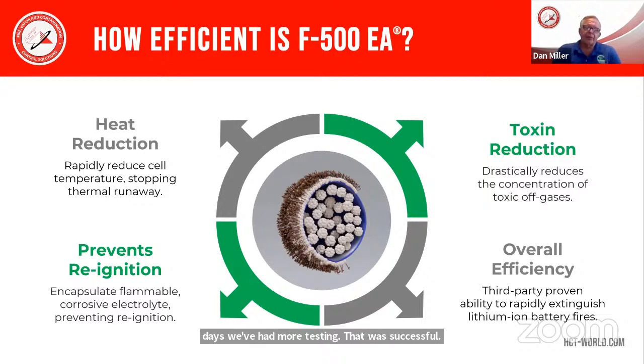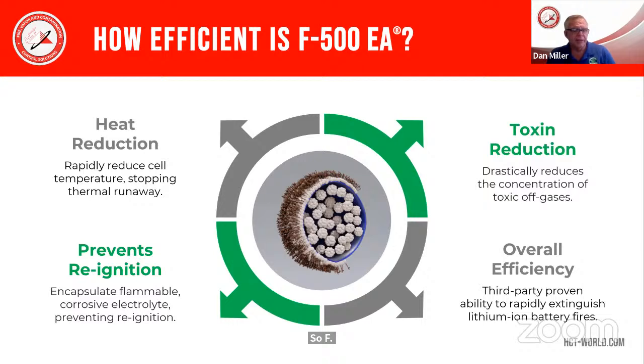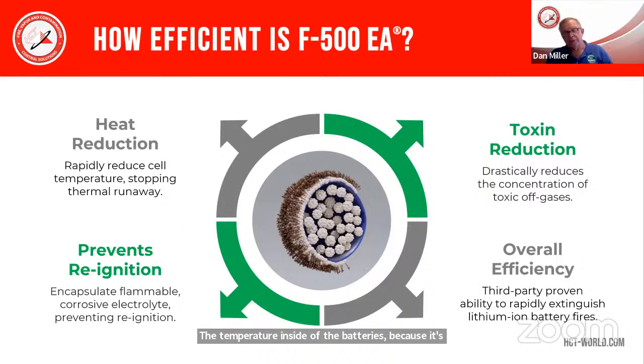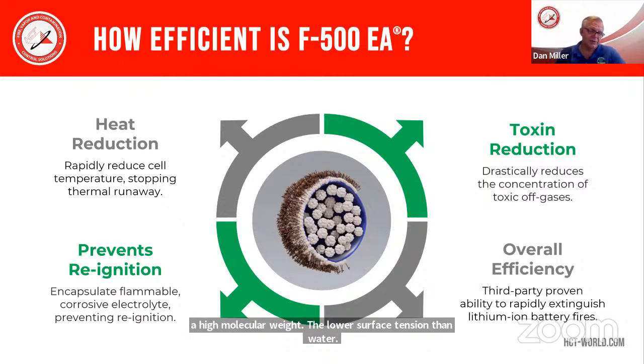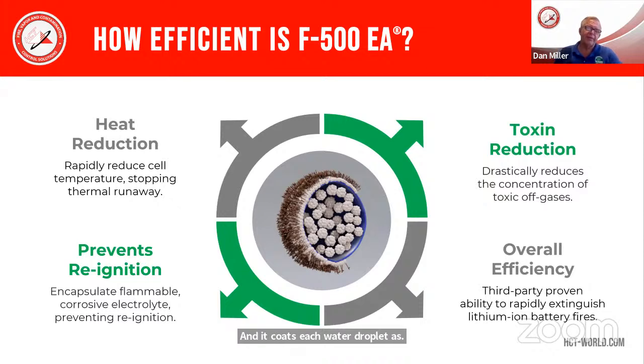F500 rapidly reduces the temperature inside of the batteries because it's able to penetrate very, very well. It has a high molecular weight, a lower surface tension than water, and it coats each water droplet, as you see in the image in the center of this slide, with a coating of F500 molecules. The heads of those molecules stick in, the tails stick out, and the heat is readily absorbed to the inside of that water droplet into those spherical micelles inside through a process we call transference. That water droplet is extremely packed full of those spherical micelles - there's millions and millions of them in there absorbing heat all the time.